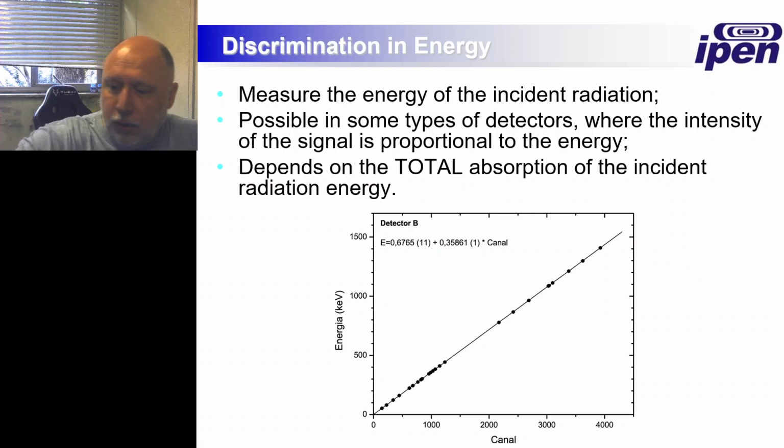If, say, this is my detector, and we have some radiation coming in here that has this range, most of these particles will exit the other side of the detector and will leave part of their energy outside the detector, meaning the detector will not be able to see the whole energy of the radiation. Now there's another type of radiation that has this range. This one will be fully collected inside the detector, and then you will have the knowledge about the whole energy deposit of the radiation, right?